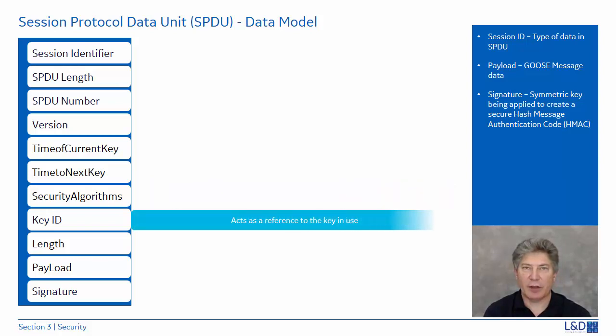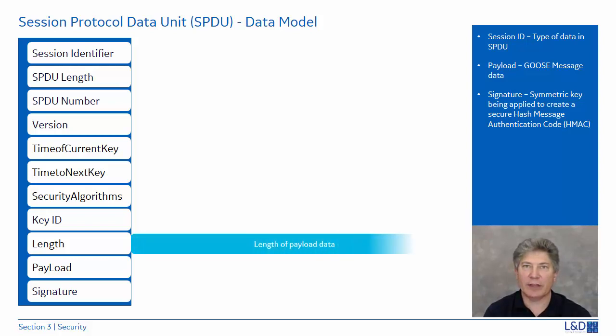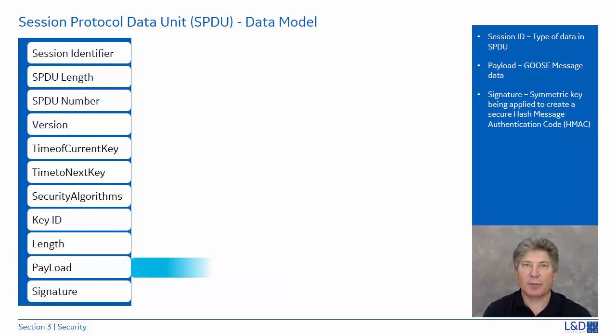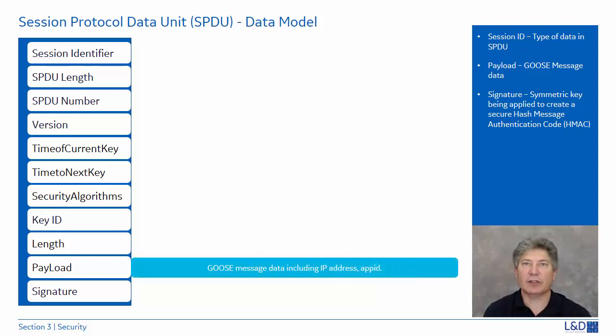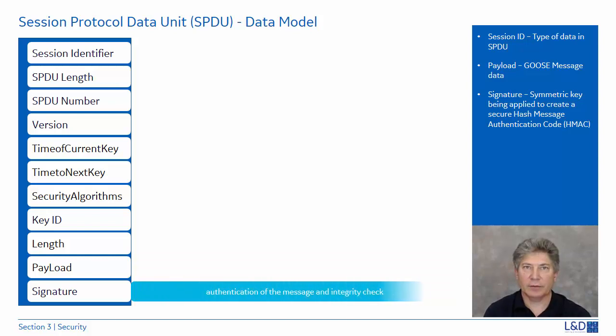Next is the key ID, which is assigned by the key distribution center, key management, and is used to lock and unlock the message and is unique during the lifetime of the security association. The length is the length of the payload data. The payload is the GOOSE message, including the simulation bit, the application ID, etc. And finally, the signature. This is a secure HMAC, which is a keyed hash message authentication code, which is like a CRC, a cyclic redundancy check, which is used for authentication and integrity checks.